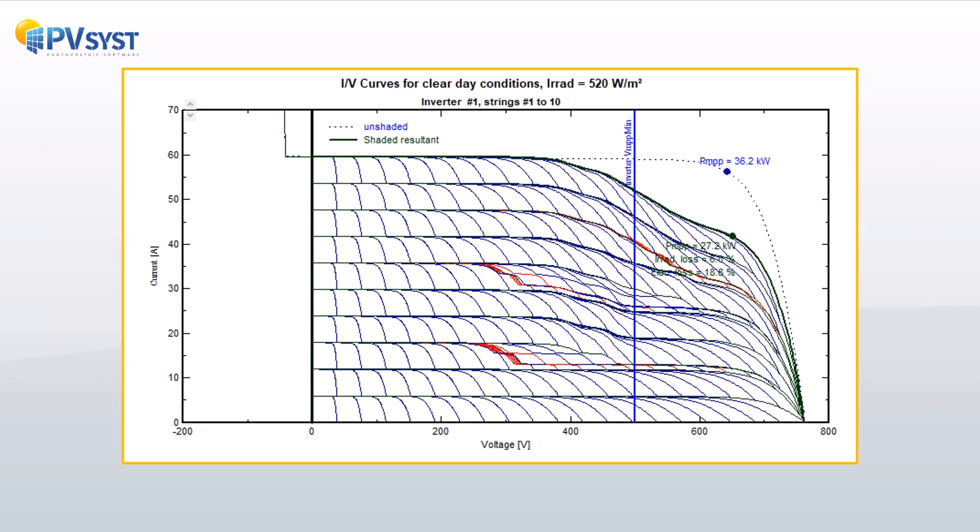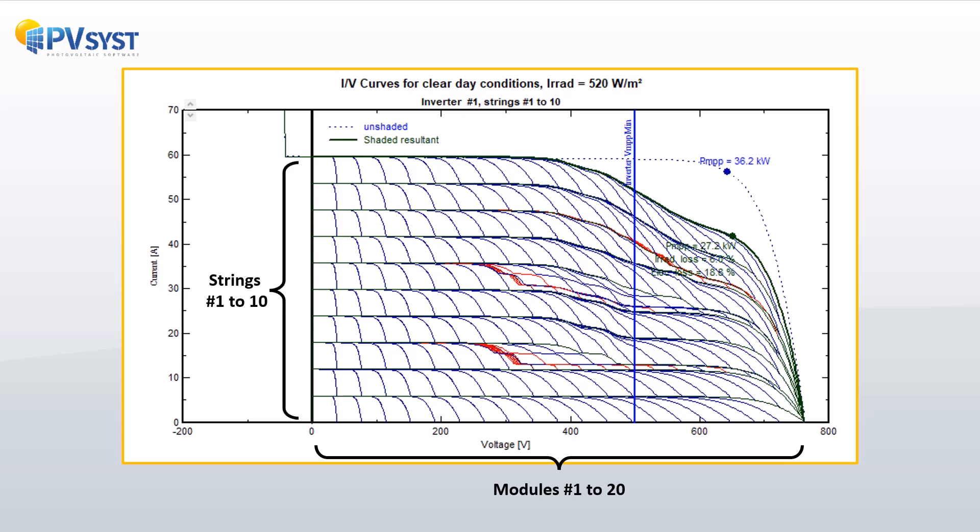To evaluate the electrical shading loss, the IV characteristics of each subarray need to be calculated. This involves combining the IV curves of each module in a string by voltage and then adding the currents for each string in parallel.